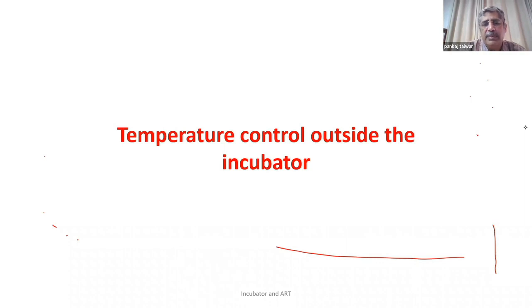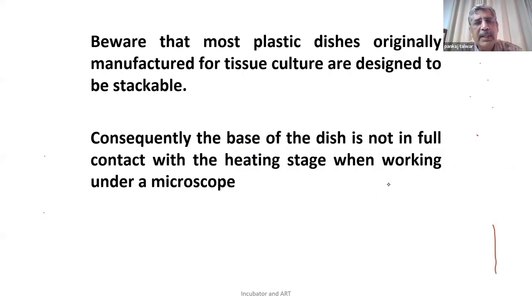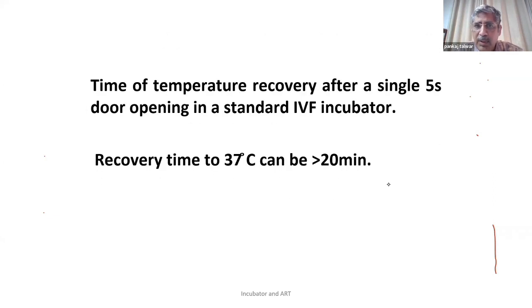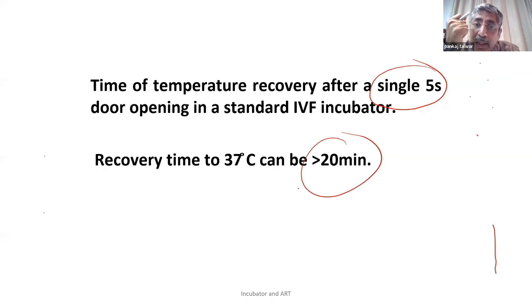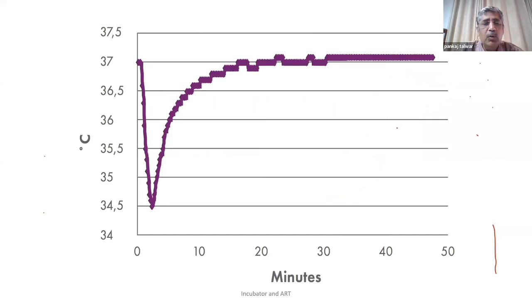So temperature control outside the incubator is also important. We have to maintain the temperature outside also. In case the temperature is not maintained outside, the incubator can become cooler. The time of temperature recovery after a single 5-second door opening can be 20 minutes. Once you open the incubator door, it can lead to temperature loss, and coming back may take even 20 minutes. Huge issue. That's the reason we are now moving away from box incubators. A single door opening of 5 seconds takes around 20 or 30 minutes for it to become stable again.